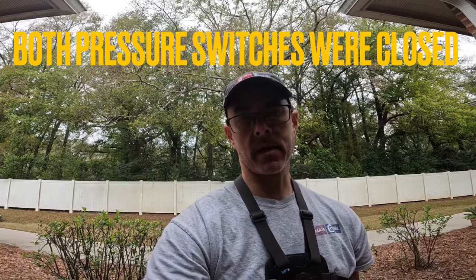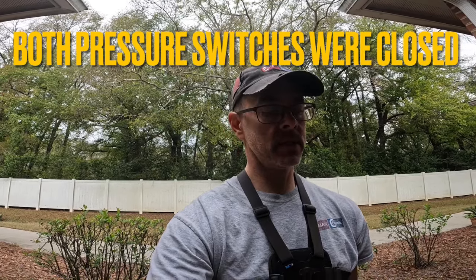I gave it some time, and maybe it, I don't know. I didn't understand why I wasn't getting voltage at the time. I tried everything. I had plenty of pressure in the system. I hit the test pins to try to speed up the timer, and nothing would work. But this callback is on me. Happens like that. I'm glad it wasn't smoke.